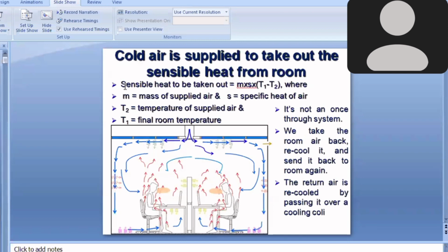So if we know how much sensible heat is within the room, and we know the specific heat of air, and we know both T1 and T2, we can find out how much air we can supply. So if we can find out the sensible heat, we can find out how much cold air we should supply in the room. And we take this air out, and it's not a once-through system. We don't take the air out and throw it in the atmosphere. We take it back, recool it, and send it back to the room.